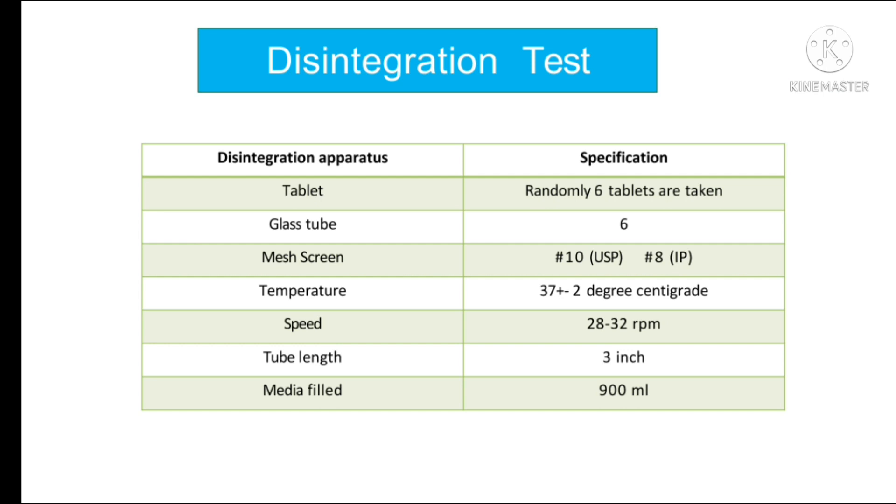The liquid is held at 37 plus or minus 2 degrees centigrade. For compressed uncoated tablets, testing fluid is usually water, but sometimes monographs refer to use of simulated gastric fluid.